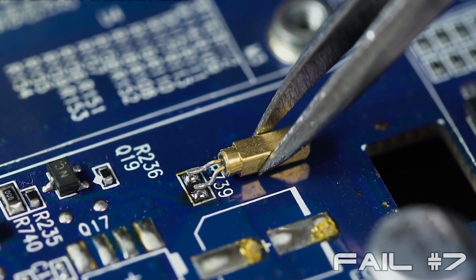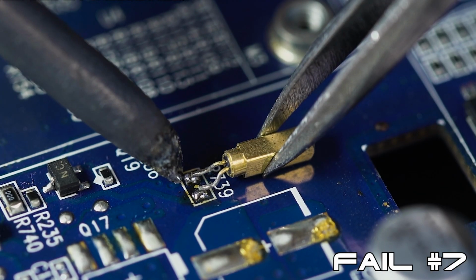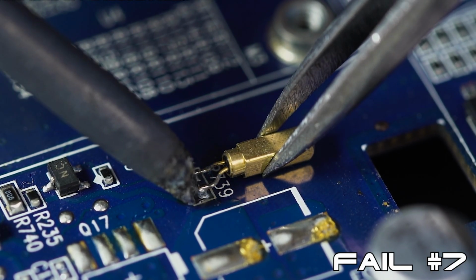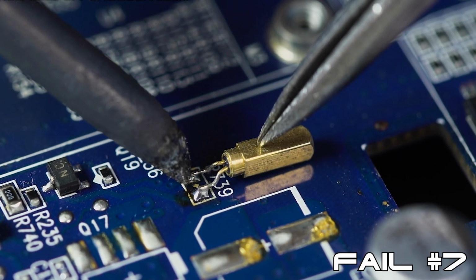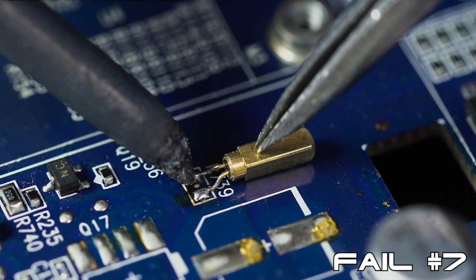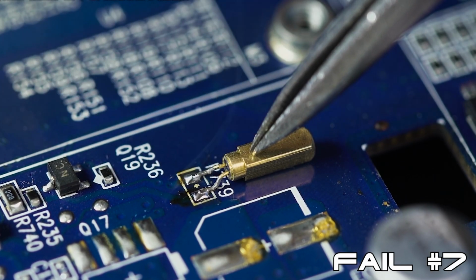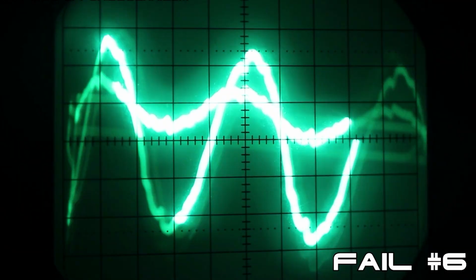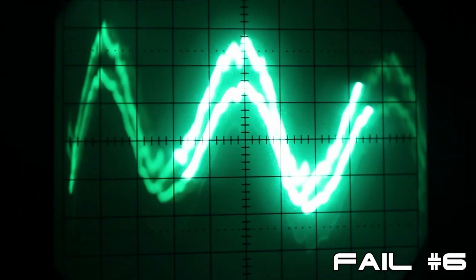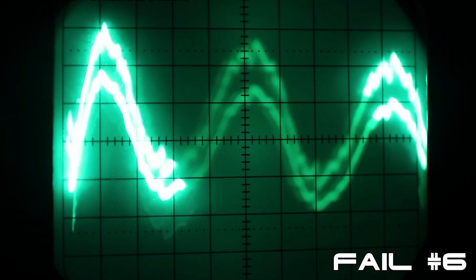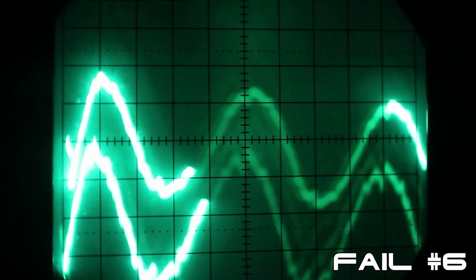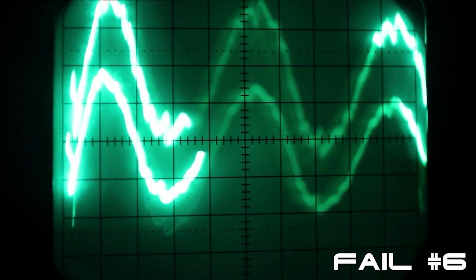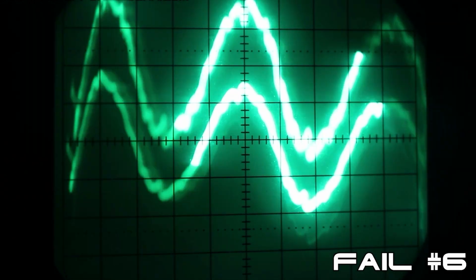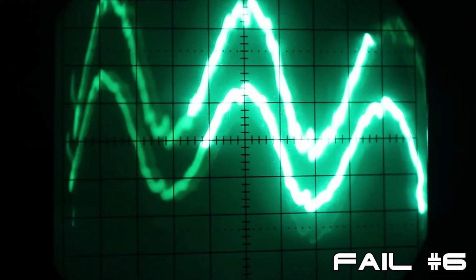Fail number 7. Because of their exceedingly complex design, high parts count, and the lack of available schematics, once the warranty on a high-frequency inverter runs out, it will be nearly impossible and expensive to find a shop that will perform repairs. That's why they're known as throwaway inverters. Fail number 6. Due to the lack of an iron core, copper-wound transformer, high-frequency inverters tend to produce a distorted waveform when starting and powering heavy or high-inductance loads. This distorted sine wave can damage sensitive electronic loads that are connected to the inverter's output. That's why you'll rarely see any YouTube affiliate advertisers with an oscilloscope connected to the inverter that they're promoting.